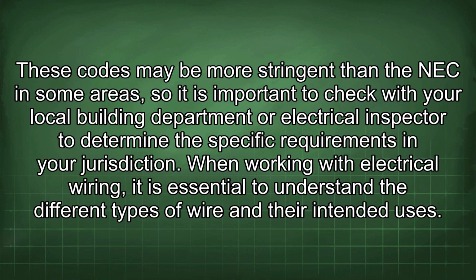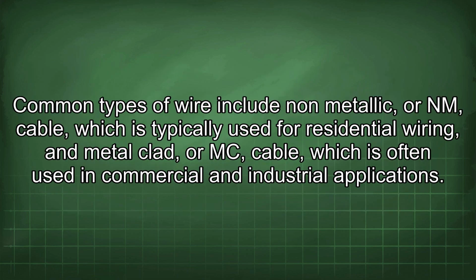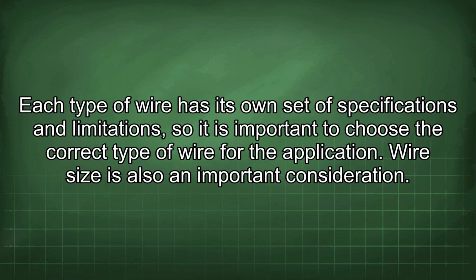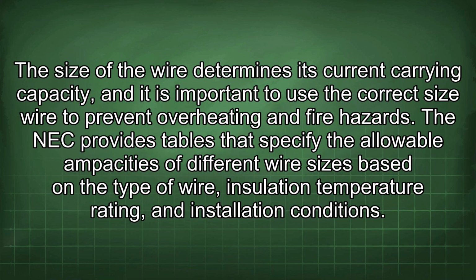When working with electrical wiring, it is essential to understand the different types of wire and their intended uses. Common types of wire include non-metallic, or NM, cable, which is typically used for residential wiring, and metal-clad, or MC, cable, which is often used in commercial and industrial applications. Each type of wire has its own set of specifications and limitations, so it is important to choose the correct type of wire for the application. Wire size is also an important consideration. The size of the wire determines its current carrying capacity, and it is important to use the correct size wire to prevent overheating and fire hazards.